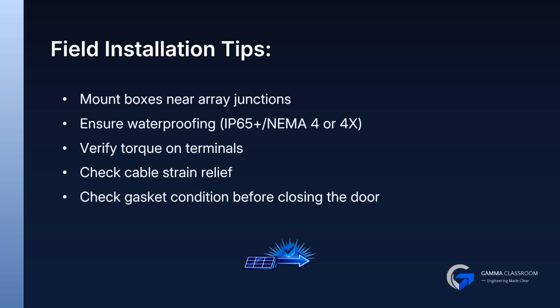Combiner boxes live outdoors, so sealing and torque checks are critical. A loose terminal can cause heat buildup and long-term damage. Proper strain relief prevents cable movement and protects terminations.